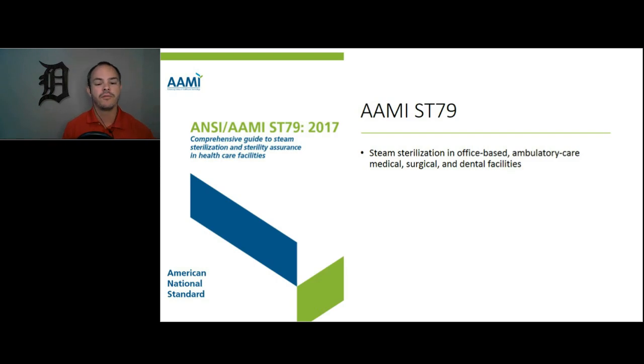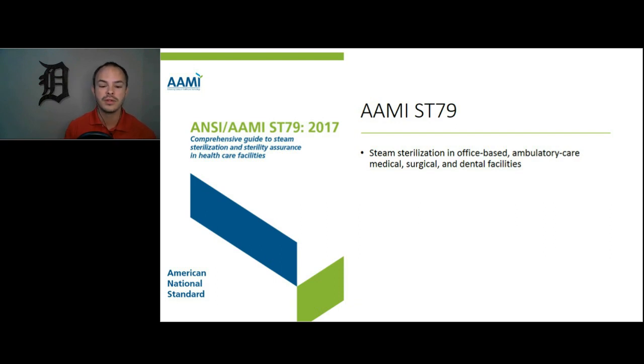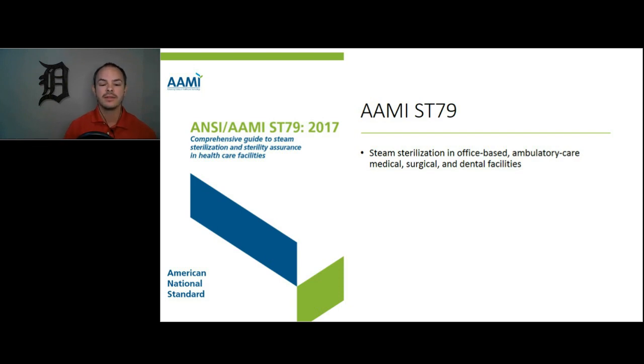ANSI/AAMI ST79 is about steam sterilization specifically, and it states that advances in medical, surgical, and dental practice have led to increased use of alternative healthcare sites like offices and ambulatory care clinics in similar clinical settings. Many such facilities use tabletop steam sterilizers. So this comprehensive guide applies to those settings as well. ST79 applies to you in the ambulatory care setting.